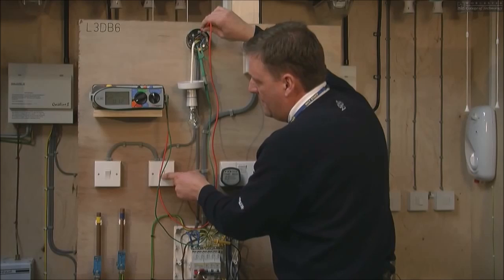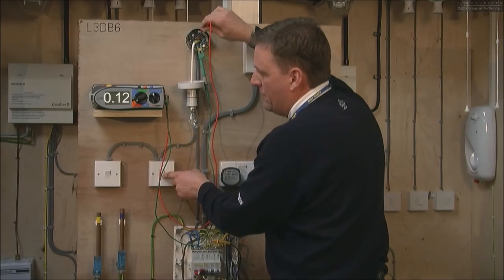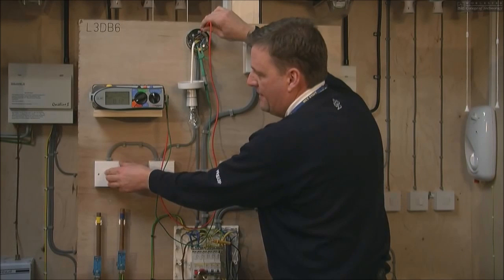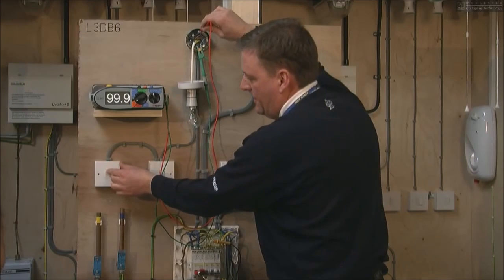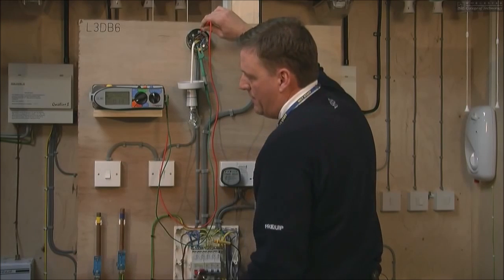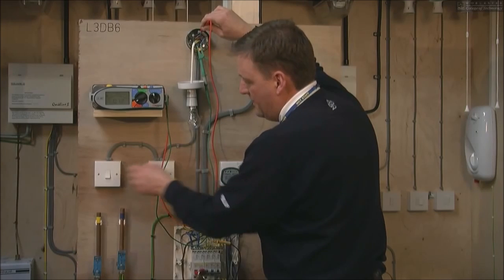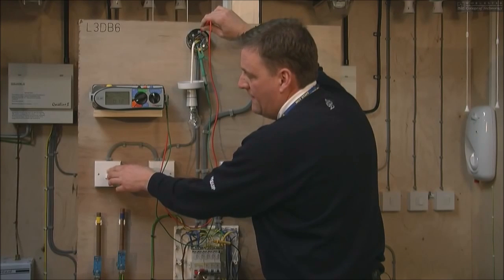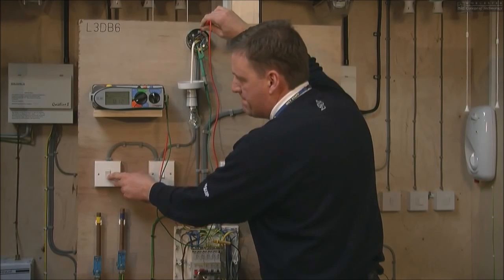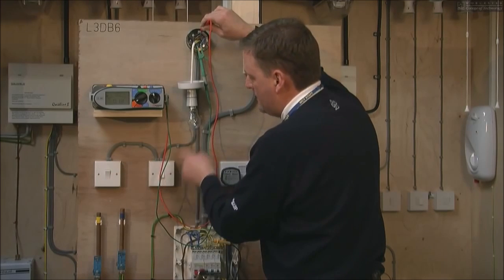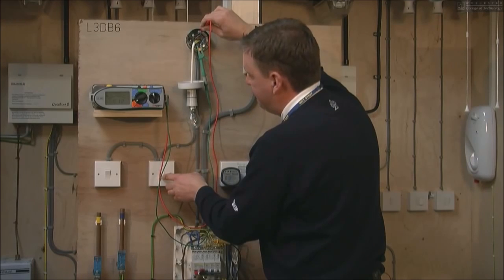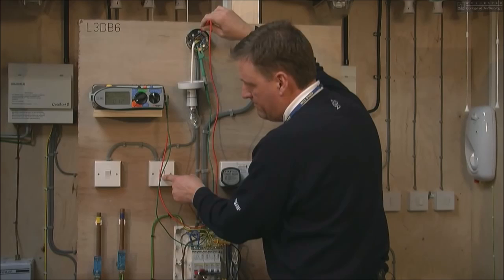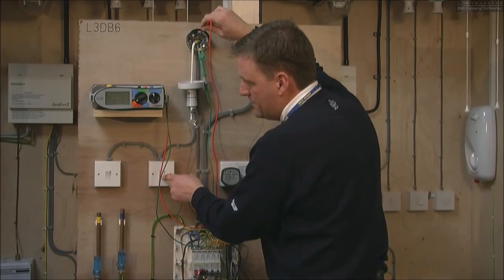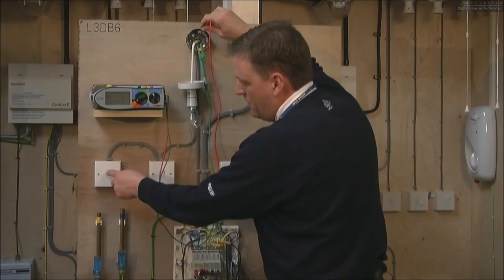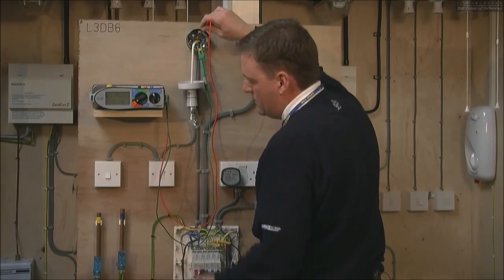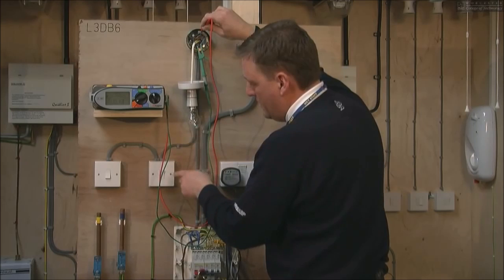We can then switch the tester on and off. As you can see, that'll go to 99.9. We can switch the circuit back on. This is actually testing the polarity also on this circuit, because we're switching the tester on and off as we would do the light. As you can see, that's switched off. That switches the circuit back on. We're basically opening and closing the line conductor.